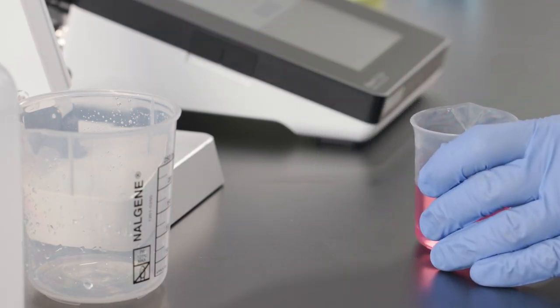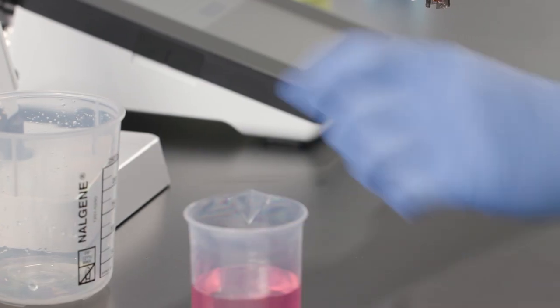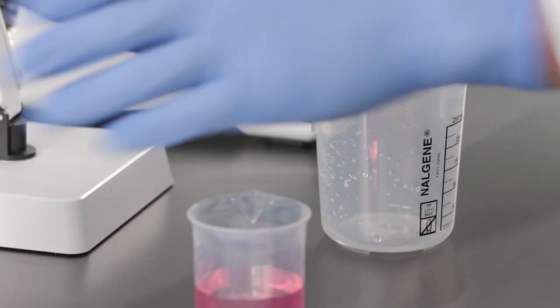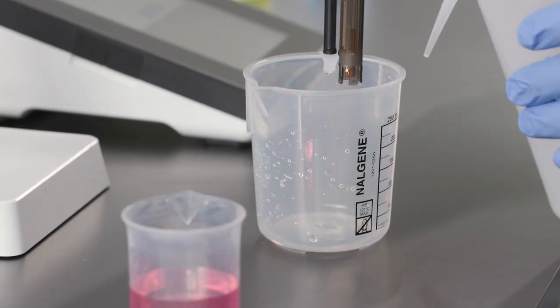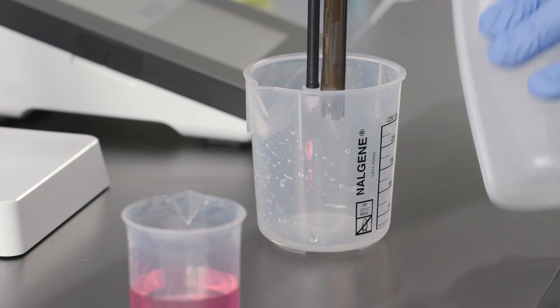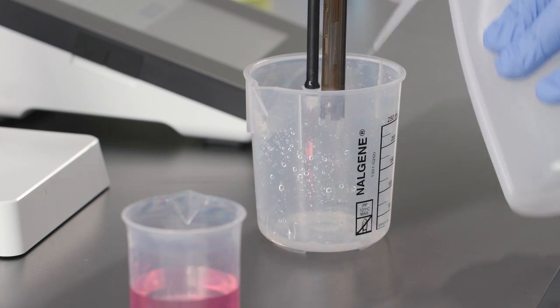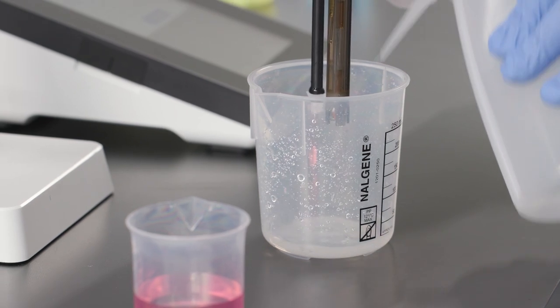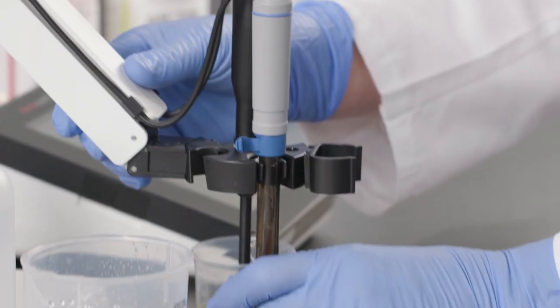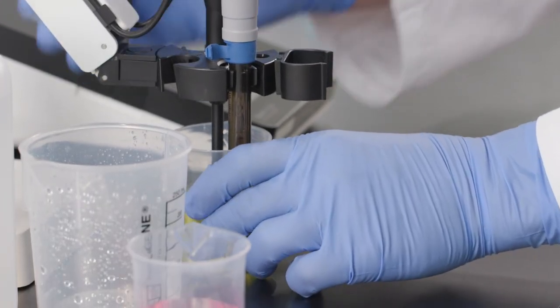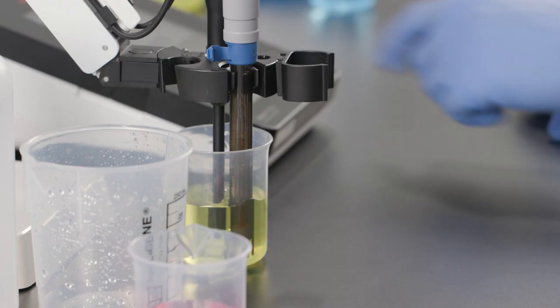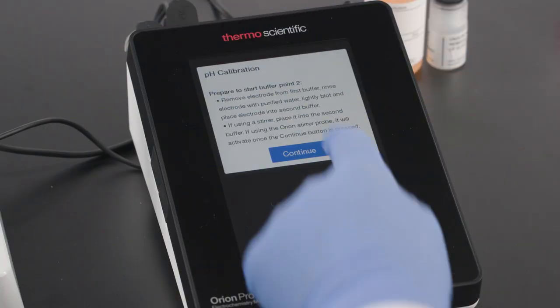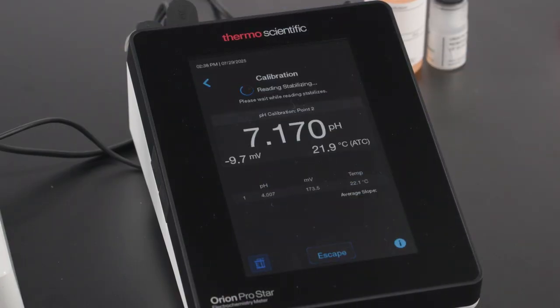Again, the Orion ProStar meter provides on-screen instructions to prepare for the next calibration point. Remove the electrode and stirrer probe from the pH 4 buffer and rinse thoroughly with generous amounts of purified water to remove all traces of the buffer. We're ready for our next calibration point. Lower the electrode and stirrer into the pH 7 buffer and tap Continue on the meter screen.